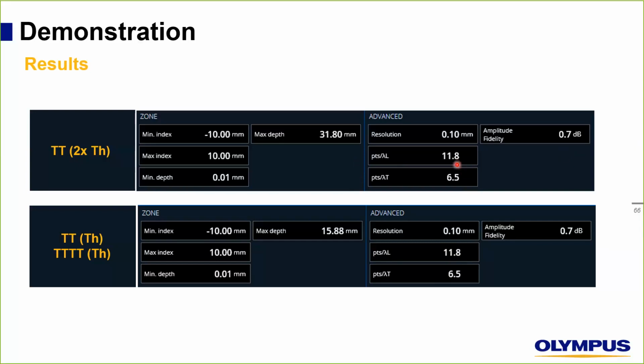But suppose that you are inspecting a 100 millimeter part, doubling the zone would mean 200 millimeter. So probably this is higher than the capacity of covering this area by 1024 points. So this may affect the amplitude fidelity. But again, the X3 will allow you to do such manipulation or such technique easily, since the amplitude fidelity and the resolution will be perfectly code compliant.